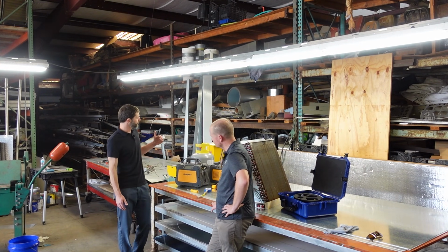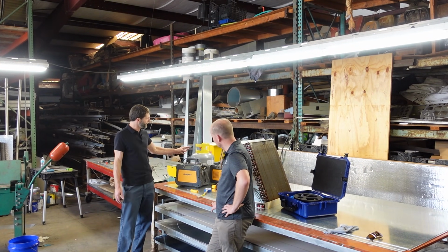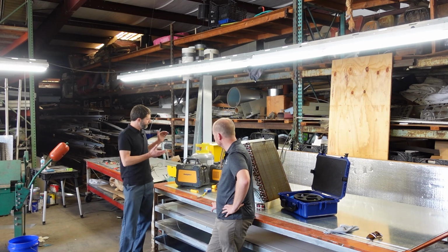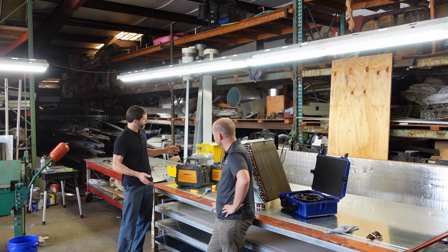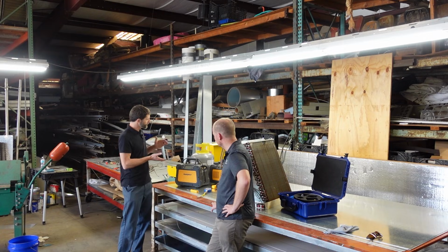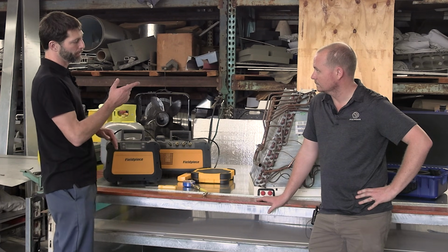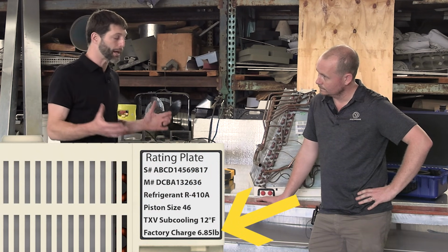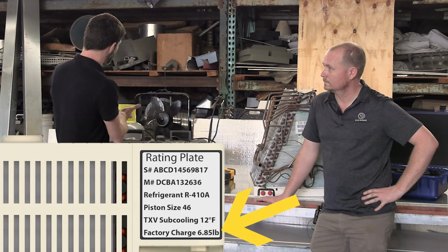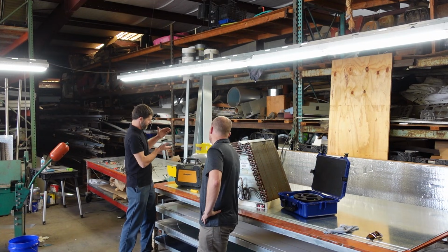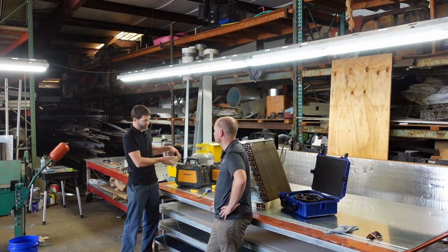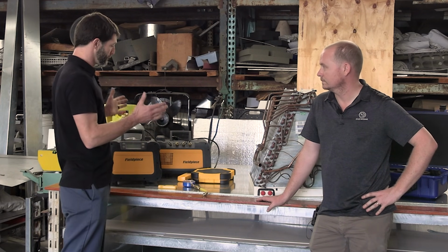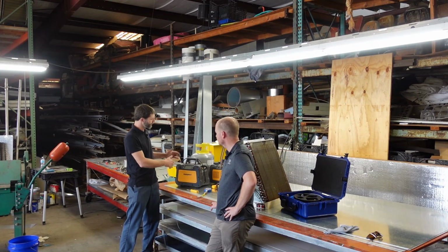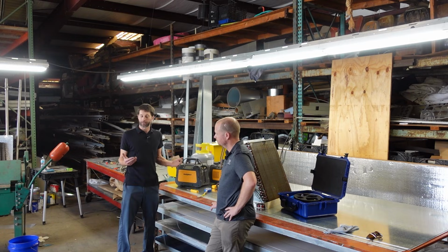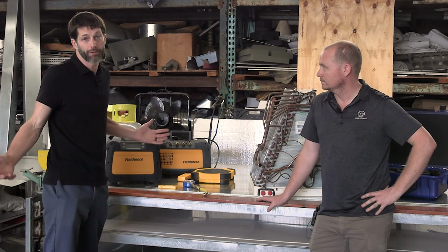So another thing to keep in mind is that you want to monitor the amount of refrigerant going into that tank. And so first you want to know how much refrigerant's in the tank, and you can look at the factory charge on the unit to see how much refrigerant you're going to be putting into that tank. You may need to basically top that tank off at 80% and then switch tanks, or you may just want to do one recovery with one tank, and so you want to kind of plan that out depending on how much refrigerant's inside the system that you're working on.